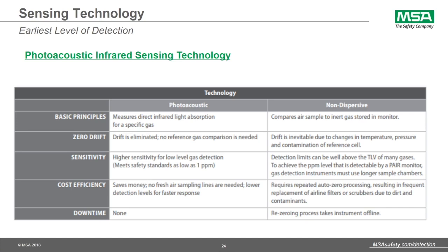For zero drift, photoacoustic is known to be inherently stable. So drift is really a non-issue because there's no reference gas comparison that's needed. For non-dispersive infrared, drift can be inevitable due to changes in the environment, like temperature and humidity. That tends to contaminate the reference cell.